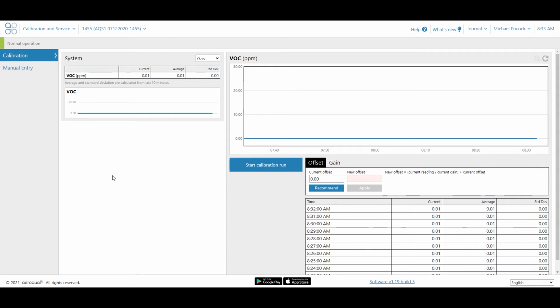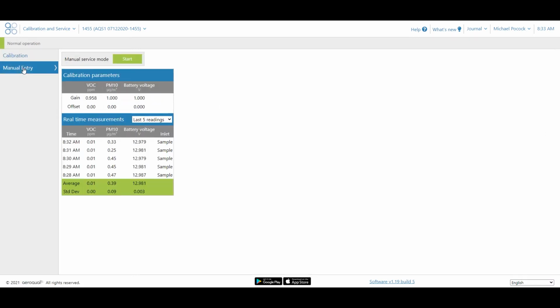The first thing that you want to do when you calibrate is go to Manual Entry and press Start Manual Service. So we're now going into service mode. It's very important to be in service mode because none of the data then gets recorded when you are calibrating. You can get some odd numbers when you're calibrating, so we don't want that data to be included in the data set. Here it says service mode pending. At some point that will say in service mode. That's just loading. We're online here.